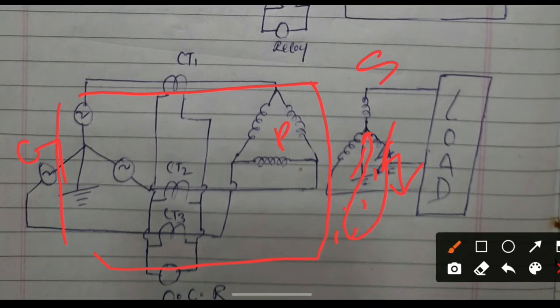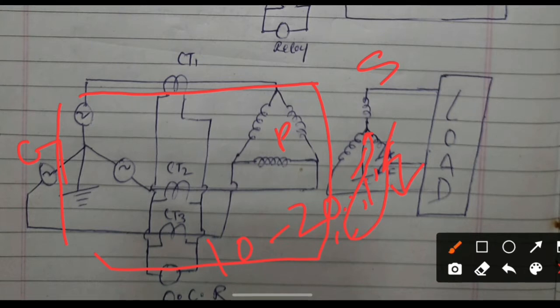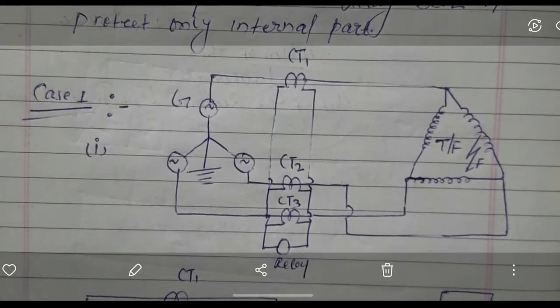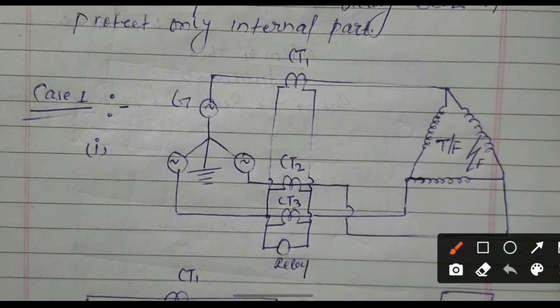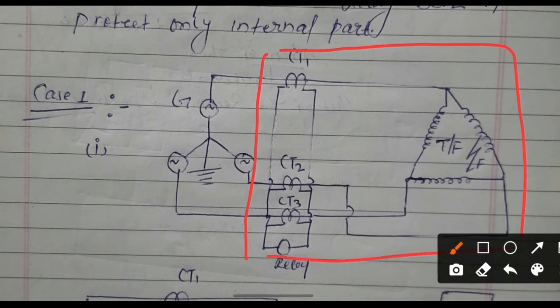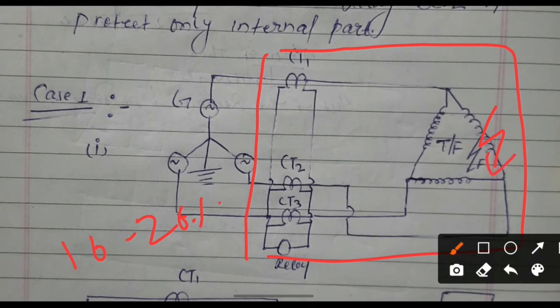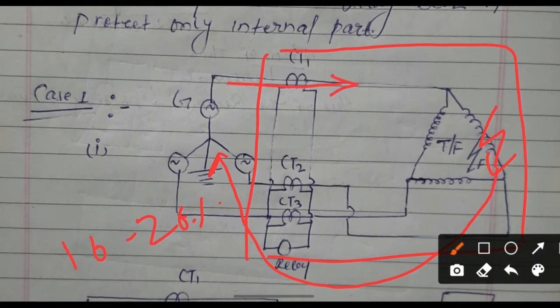If the fault is minor — only 10 to 20 percent — then it will not get effect on the delta side. The positive, negative, and zero sequence currents will not sense any current on the delta side, and the relay will not operate. But if the fault occurred in the internal zone of the transformer — this is our protection zone — the relay is set at 10 to 20 percent of rated current. Suppose the fault occurs here; this fault current flows through the generating side and through all the CTs.